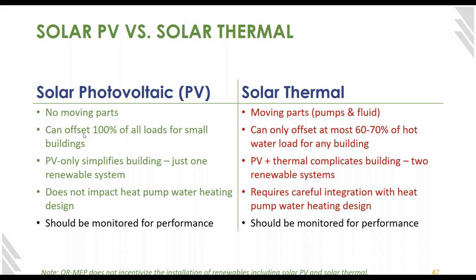With gas water heating and solar thermal, you hook them up, preheat the water going into the gas water heating system, and you're done. Engineers and contractors have been doing this for decades and know how to get it done. With heat pumps you can do that too, but we're seeing that hot or warm incoming water actually significantly reduces the efficiency of heat pumps. Because heat pumps are so efficient, it makes more sense to go with PV instead of thermal.